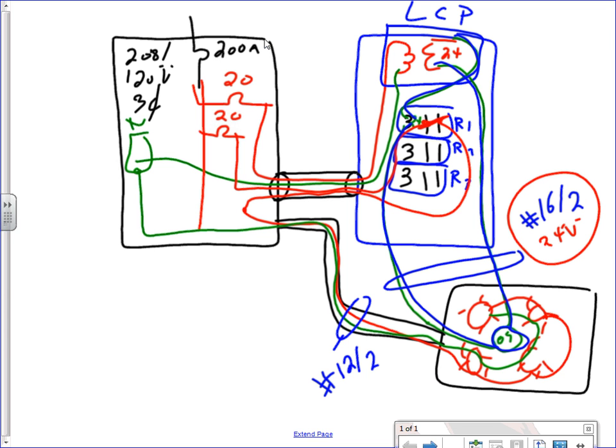An occupancy sensor is essentially a fancy switch. Instead of walking to the wall, the occupancy sensor detects you're there and triggers a mechanism that turns the switch on — keeps it on for 50 minutes, and if no motion is detected it opens. They use two technologies: one can hear you — ultrasonic — and one can see you using waves — passive infrared. So if you're moving or making noises, it will turn on.